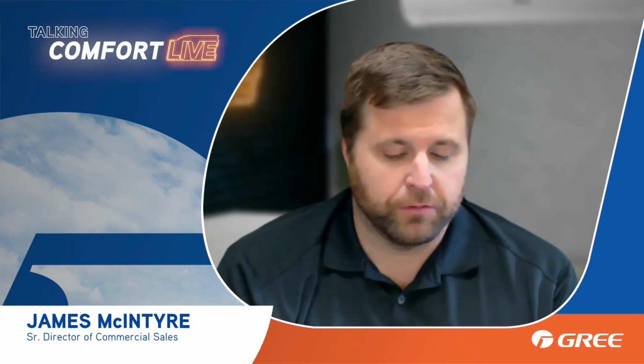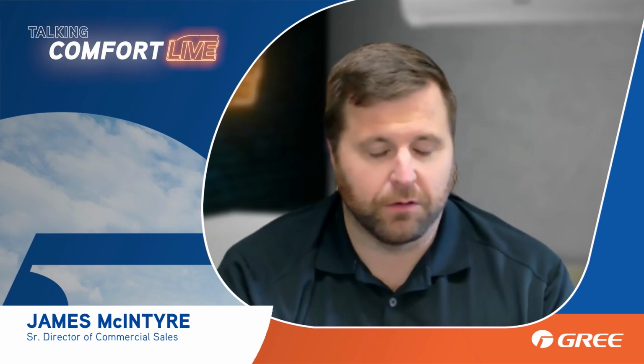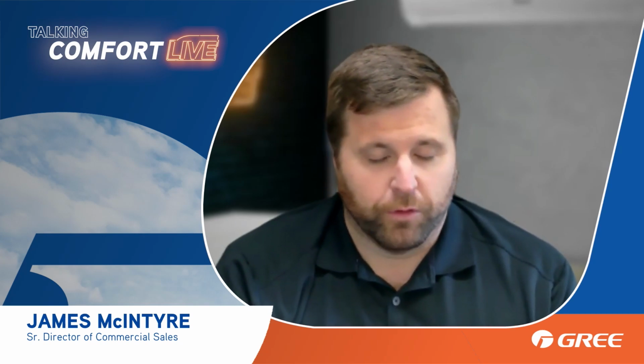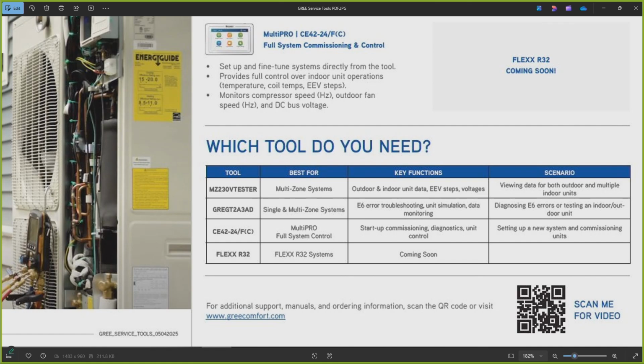It gives you the hertz of the system, and on those systems you can have a whole lot of thermistors, temperature sensors. You've only got so many thermocouples you can hook up to go measure temperatures, but this has got every single data point for those sensors, so you can see all those temperatures simultaneously. You can see the performance of every indoor unit on the system.